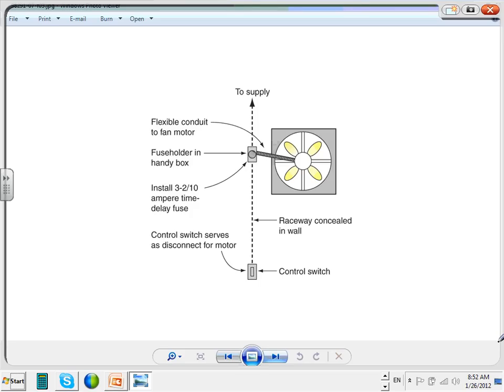The snap switch, yeah. I'll show you one in our lab. Some of these, if this is a controller, it is actually for bigger motors than fractional. For up to 2 horsepower, you can have a snap switch like this, with an overload inside it. If you go to our lab here at Dunwoody, I'll show you. It looks exactly like one of these. You cannot tell by looking at it, but if you open it, you'll find a place where they have overload protection in it. The standard little one that you buy will work for a fractional horsepower, as in a quarter, a third, like the bathroom fan in your house.